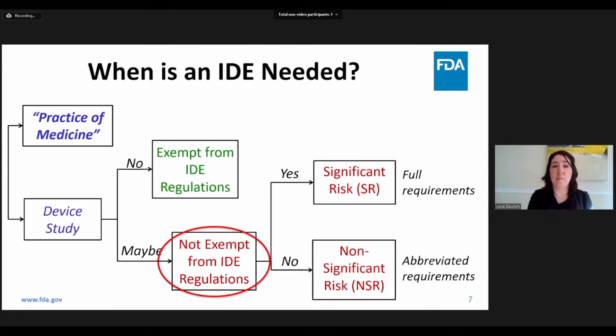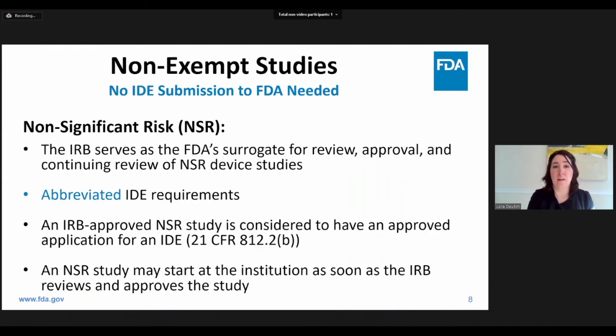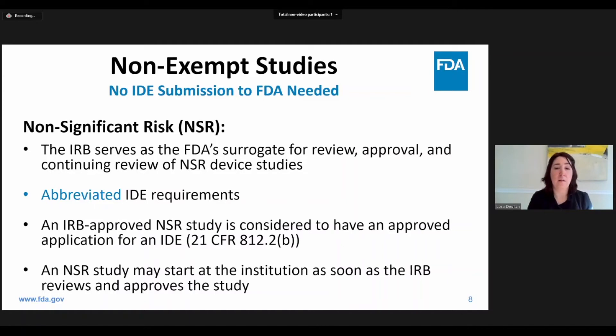If the device is not exempt, there are two kinds of studies that need to comply with the IDE regulations: significant risk studies and non-significant risk studies. Non-significant risk studies do not meet the definition of a significant risk study. These studies do not require an IDE application approved by FDA, as the IRB serves as FDA surrogate. There are a subset of IDE requirements that need to be met, including labeling requirements, informed consent, IRB approval, and others. A non-significant risk study can start as soon as the IRB reviews and approves the study.